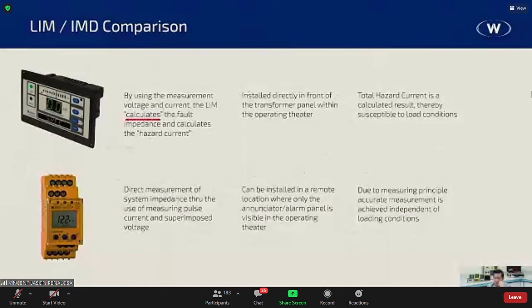Now, physical differences, as you can see, one is the size. The next one is the way it is installed. Now, the line isolation monitor is basically installed directly in front of the transformer panel within the operating theater. So you have your whole panel inside the operating theater. You have your circuit breakers there. You have the line isolation monitoring there, as well as the transformer. Now, you probably all know transformers, these are dry type. Chances are you will need to maintain them at one point, right? You're going to have to clean them at one point. So the maintenance guys cannot just go inside operating theaters with their dirty safety shoes, no?